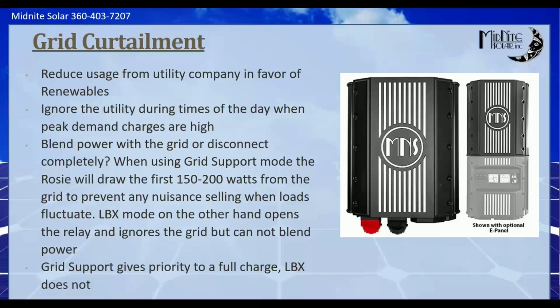And I'm gonna go over why you might want to use one of the three modes versus the other one. I'll hit on some of it here, and then we'll dig deeper when we get to those modes. But essentially, we can set it up to ignore the utility during times of the day using time transfer. So let's say your utility says, hey, between the hours of 5 and 8 p.m., we're going to charge you 3 times the normal rate. Well, we can set Rosie up to disconnect from the grid at 4:45 and reconnect at 8:15 so that you never use that expensive electricity, right? We can dig into the battery a little bit, charge it back up tomorrow.